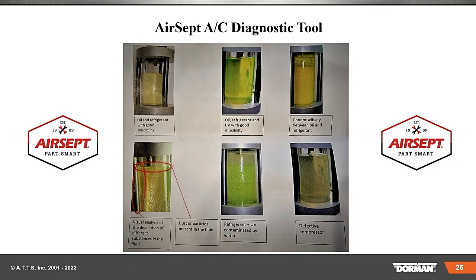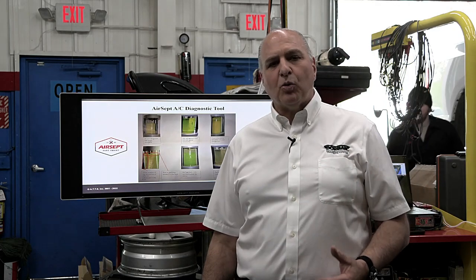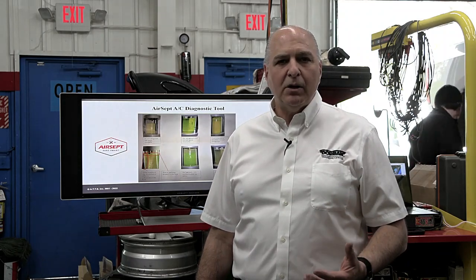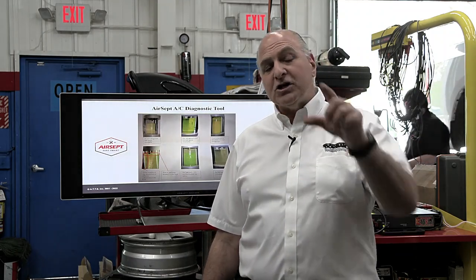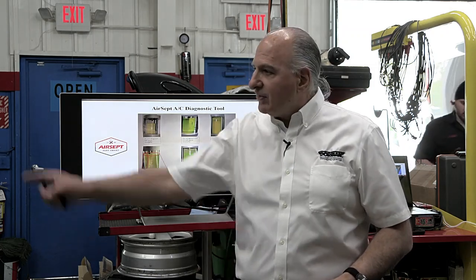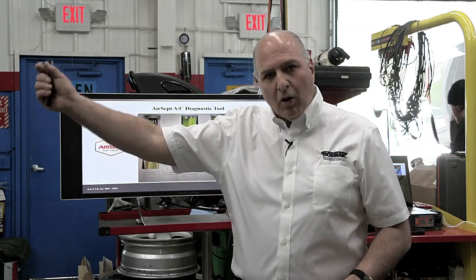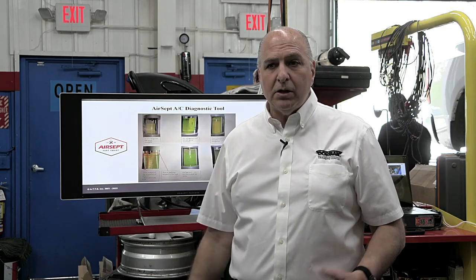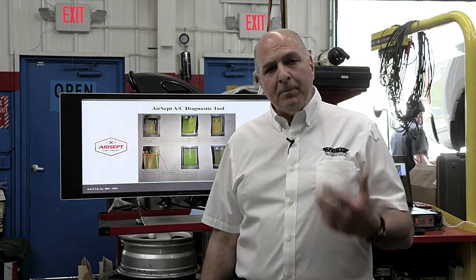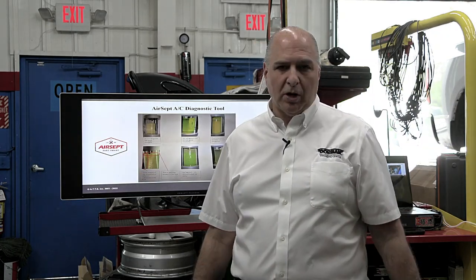And when you look at it, here is the miscibility, basically looking at good versus some bad here. So take a look at that. This is important, getting that sample. How do you know your compressor wasn't slugged, isn't pumping? Well, you could see it right from here. You could see if you have too much dye or oil in there. If that thing was stained with oil and the oil was still in the unit, you would have a problem, okay? People love putting oil in, especially with an oil bottle.